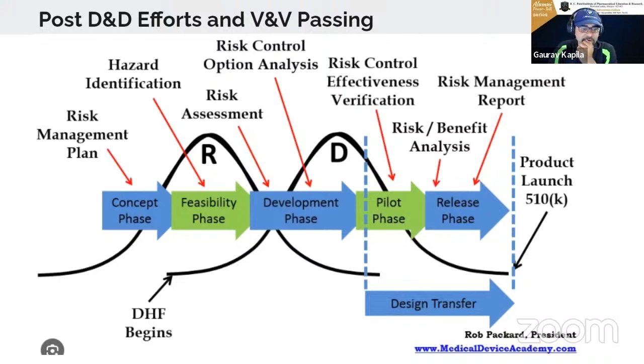Then you go with the final risk verification. After you deploy the control mechanisms, you need to verify whether your risk control is really working, or is it only in theory, but you need to demonstrate it practically. So we have to again do some kind of verifications for the risk activities if you make some design changes. And finally, when we reach the system level, we study what are the residual risks which cannot be reduced or mitigated beyond a certain point. Are they still there? And what is the overall benefit of using this medical device? If the medical device risk profile is very huge compared to the benefits it's going to offer, then it is not approved, it is never launched in the market. The product is only launched when the benefits outweigh the risks, right? So that's how the risk and the development cycle play in harmony all together.